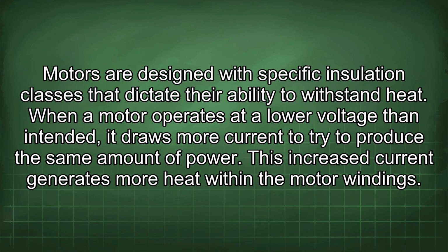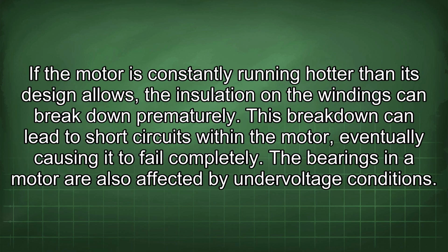Motors are designed with specific insulation classes that dictate their ability to withstand heat. When a motor operates at a lower voltage than intended, it draws more current to try to produce the same amount of power. This increased current generates more heat within the motor windings. If the motor is constantly running hotter than its design allows, the insulation on the windings can break down prematurely. This breakdown can lead to short circuits within the motor, eventually causing it to fail completely.